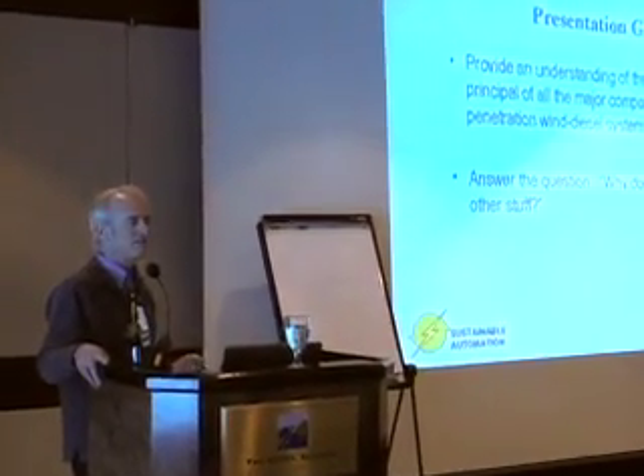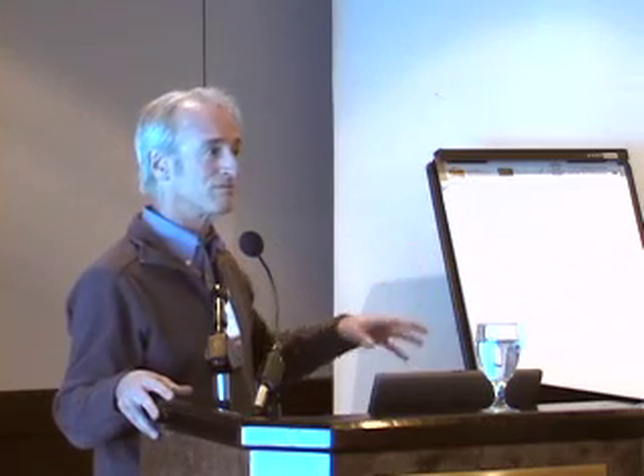And you get a lot of sticker shock when people first are contemplating going the wind diesel route, because they initially think, well, I've got the diesel power plant, I just need to add the wind turbines, right? And no, it's not that simple. What's shocking is when they find out that on a small system like Wales or Kokonok, the balance of system can cost just as much as the installed cost of the wind turbine. People step back and say, whoa, when they hear that. But fortunately, as the systems scale up, that ratio goes down. It adds considerable capital cost to the system to be able to go high penetration, but the economic benefits are ultimately there.